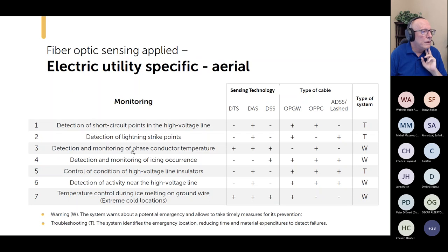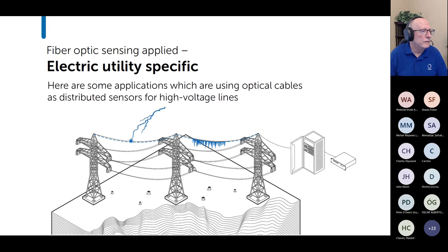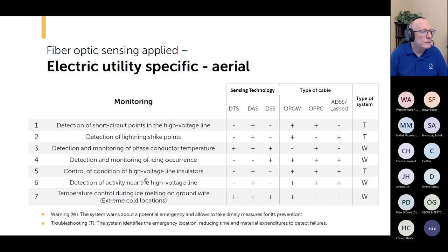Control condition. With distributed acoustic sensing on any type of cable, you could be hearing the sounds of an imminent failure on an insulator. Now, that does have a complication there. You have to have good filtering to filter out background noise. But in theory, you can do that.